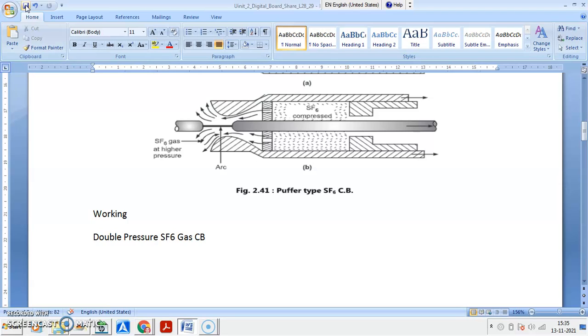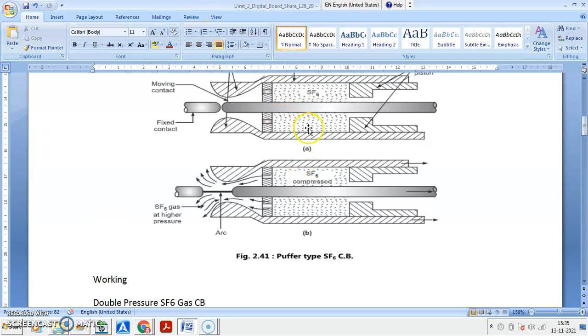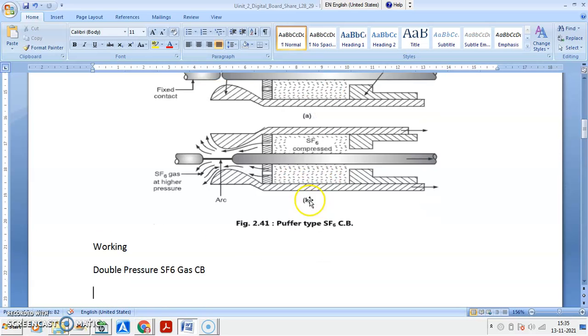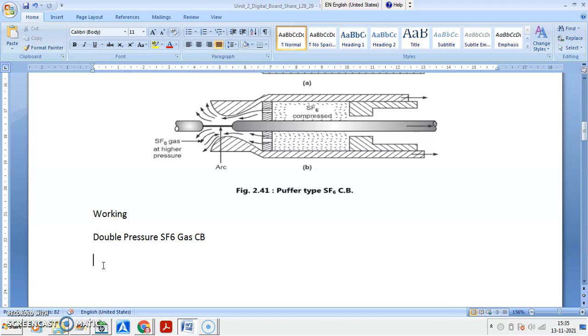in which you are having the gas stored in the tank. So now here you are having the gas in this particular circuit breaker. Here SF6 gas is under normal atmospheric pressure. Here it is compressed at high pressure. But here in this you are having the tank provided and you are having high pressure SF6 gas. From compressor it is taken, and it is stored in the reservoir like a tank.